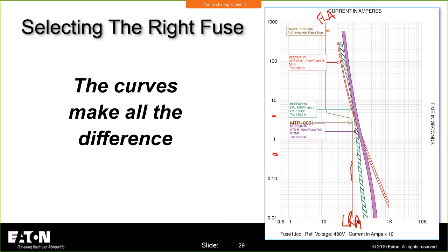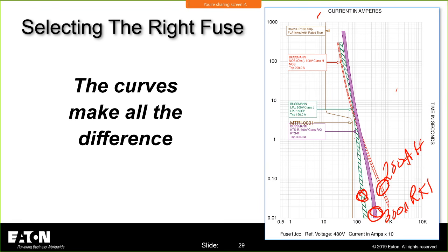So the curves, and again, for large motors is typically when we're going to be plotting damage curves or motor start curves. But if you look at these three different types of fuses, this Class H fuse is a 200 amp fuse. This purple one is a 300 amp fuse. And this is an RK1. This is an H, and the green one is a J, an LPJ Class J fuse.